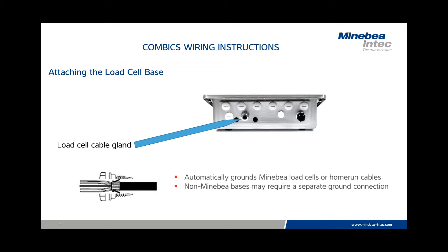If we have a Minebea load cell base or home run cable, the cable itself will have a shield grounding mechanism that, when pushed through the cable gland, will automatically ground the base. On non-Minebea bases, it may be necessary to connect a separate ground connection.